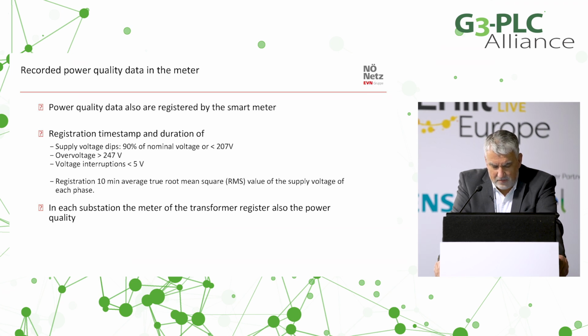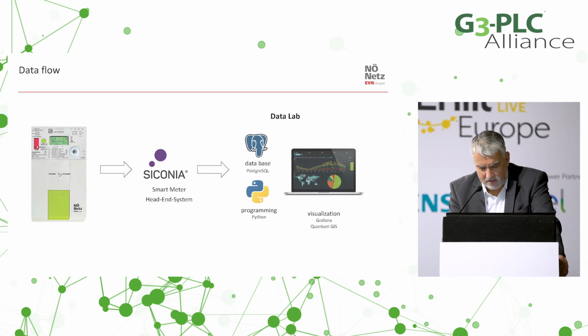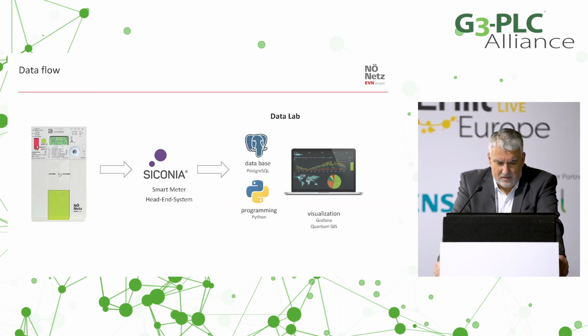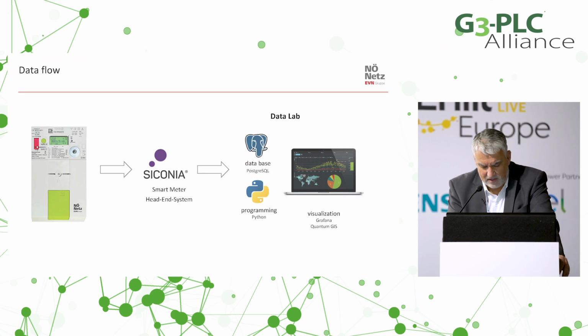Also, at all meters we register the 10-minute voltage value of the supply of each phase, and in each substation the meter of the transformer registers all the power quality data. Our system: we read the meter with our head-end system, but we don't bring the power quality data into our meter data management system. We have a separate database where we evaluate this data, and we use it especially in the GIS system to get a very quick first overview of the power quality in the grid.